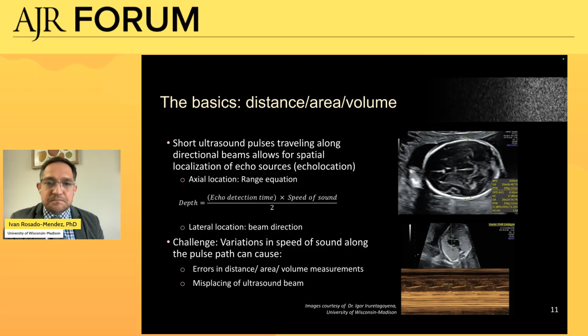Some of the challenges of the application of echolocation in ultrasound is that it depends on knowing the speed of sound of tissue or assuming a value in the calculation of the depth. Of course, when there are variations in the speed of sound, that can lead to errors in our measurements of distance, area, and volume. And it can also result in misplacement of the sources of echoes in the images. And some of the conventional or more used scenarios of the measurements of distances, areas, and volumes are, of course, in obstetrics when we perform morphological ultrasounds.